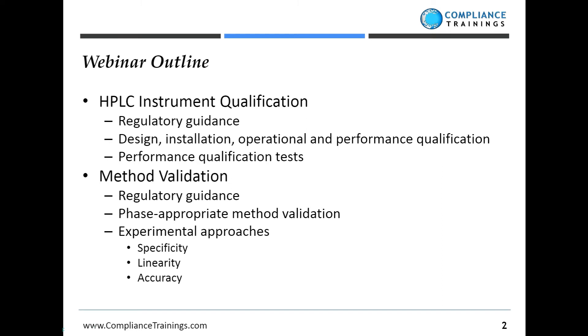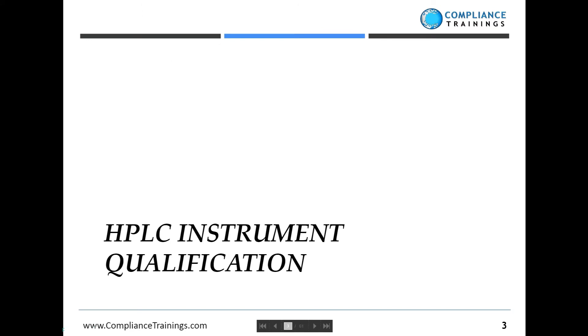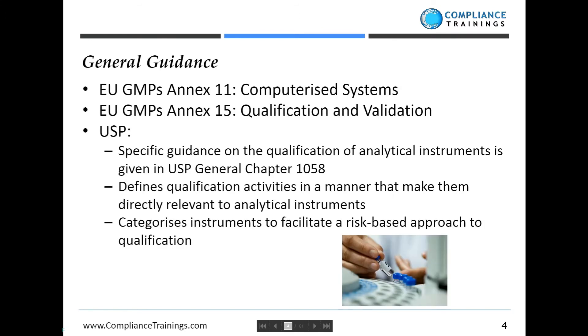So let's start off with HPLC instrument qualification. In the European Union we have guidance around computerized systems in Annex 11 and in Annex 15 on qualification and validation, but there's nothing very much by way of specific guidance in EU GMPs about analytical instrument qualification.